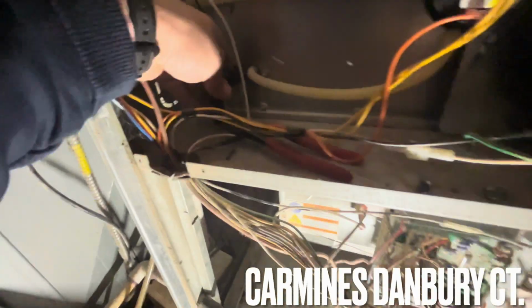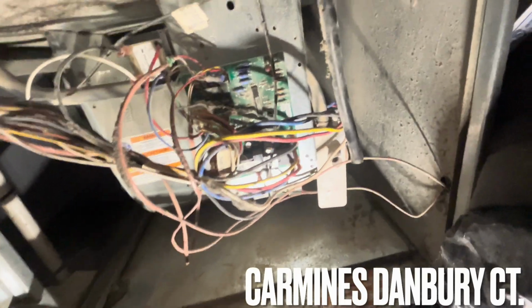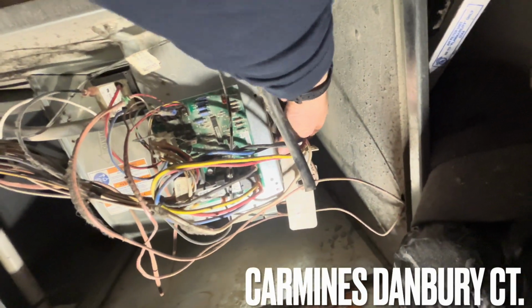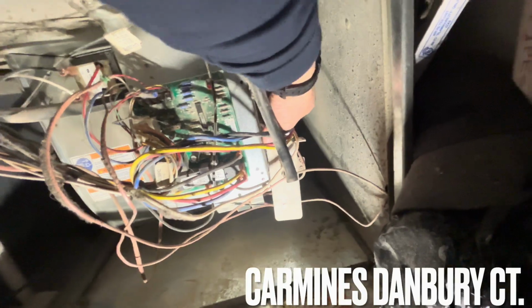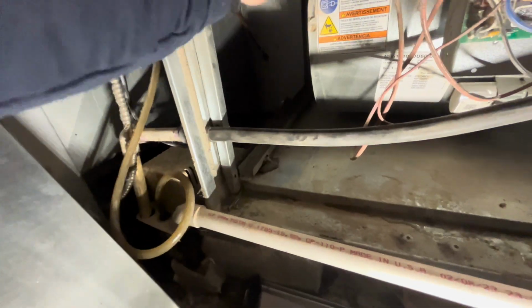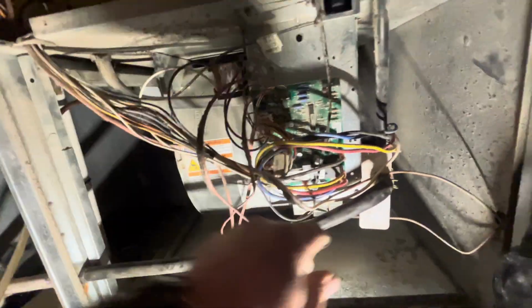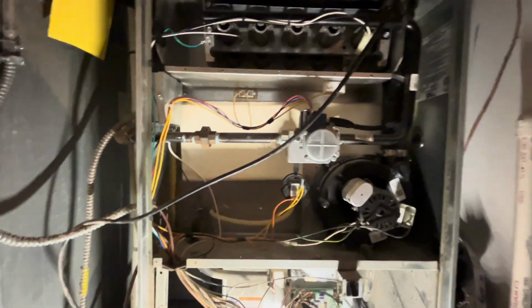High efficiency, standard efficiency, let's see if we can get some water to come out the trap. Well, I should take this off too. Hold on, let me get it. How we do it, I clean that out, clean that, trap's clean, it's on. All right, flame sensor's clean, let me start it up with it open.